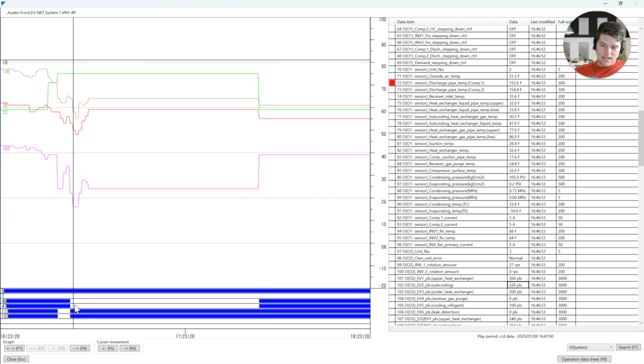It's shifted, and it takes some time. Why is it taking so long? We're at 71 and 80.6. It should not take this long. If we look at these two snippets right here, between the first and the second, I'm already into the same amount of time, if not close, as my first defrost cycle on my other unit, and it's taking twice as long, and I still haven't even gotten hot yet. This is a second key indicator that there is a charge issue on this system.